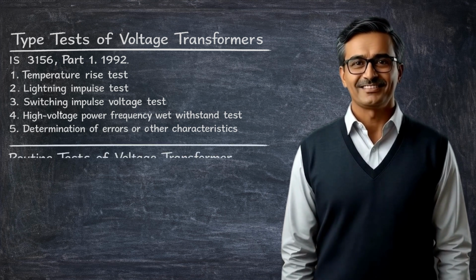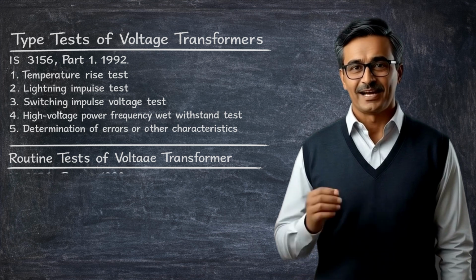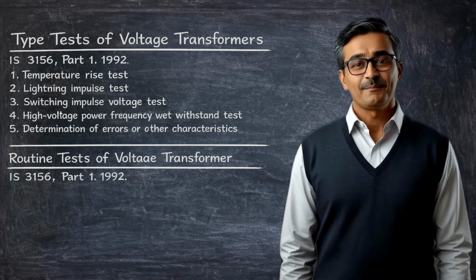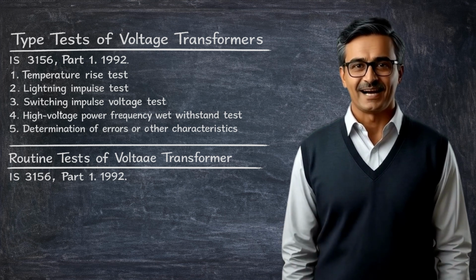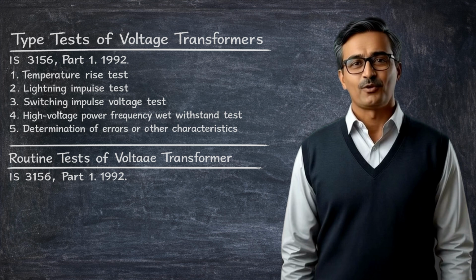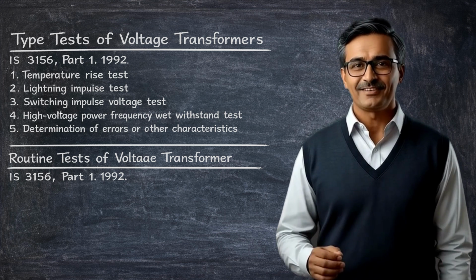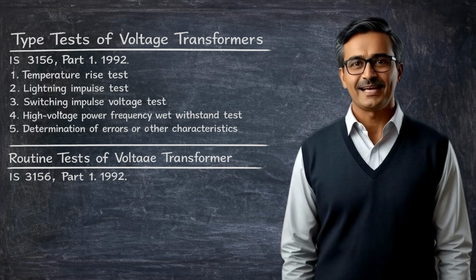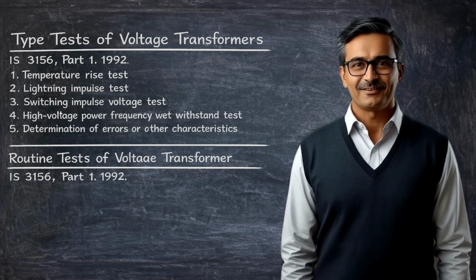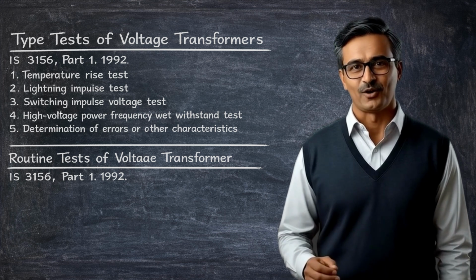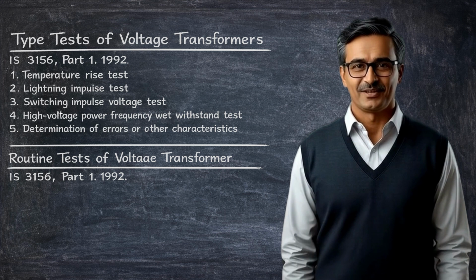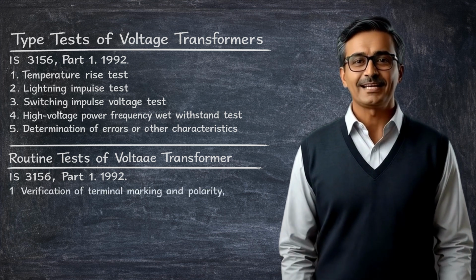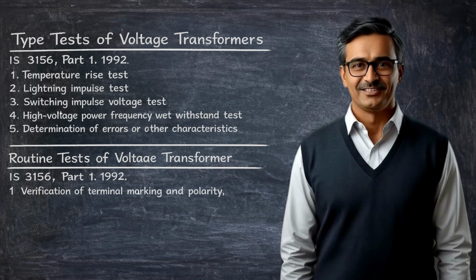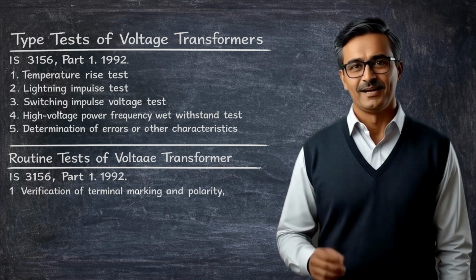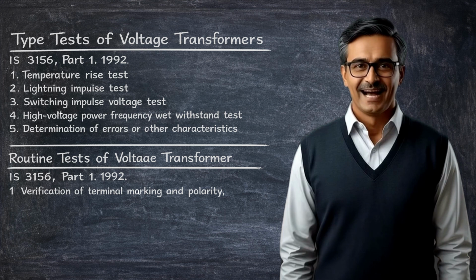In this section, we will discuss the routine tests of a voltage transformer according to IS 3156 Part 1, published in 1992. Routine tests are the tests that manufacturers perform on every voltage transformer after completing the final manufacturing in the factory. These tests ensure that the transformer is properly manufactured and safe for operation. According to the standard, the following tests constitute the routine tests. First is the verification of terminal marking and polarity. In this test, we check whether the terminals of the primary and secondary windings are correctly marked. We also verify the polarity of the transformer, which is important for proper connection in protection and metering circuits.